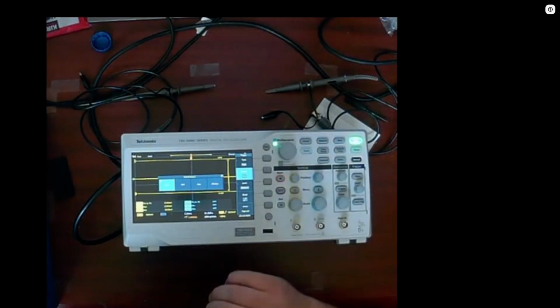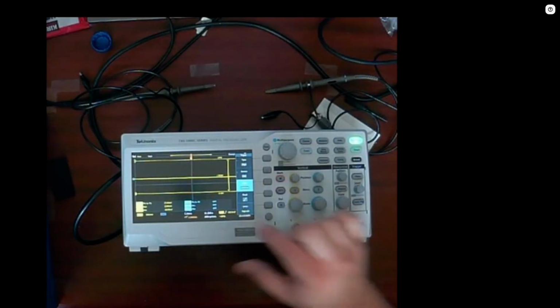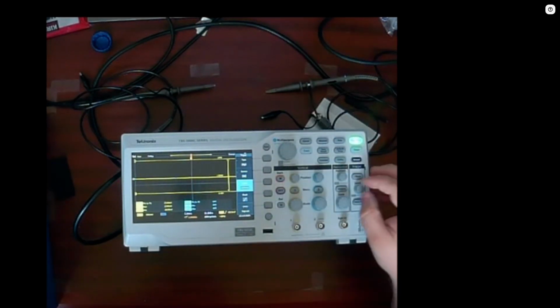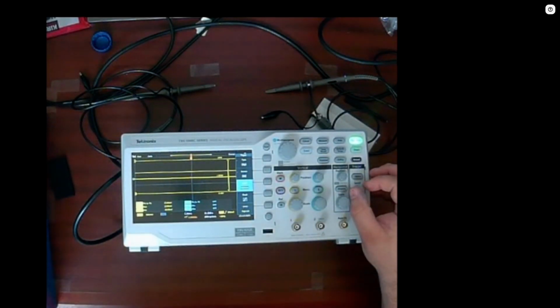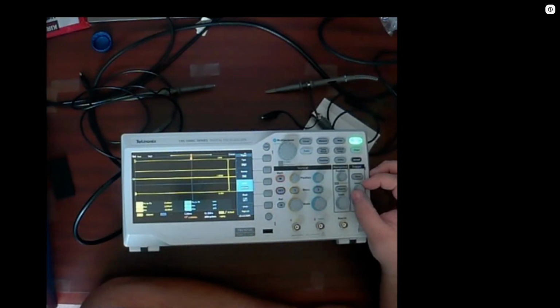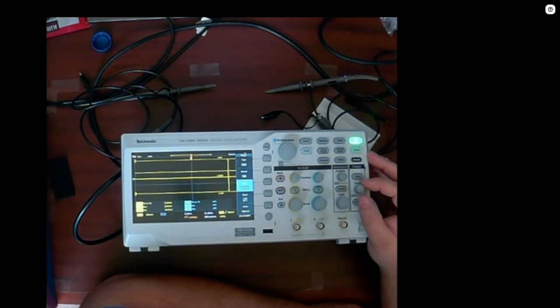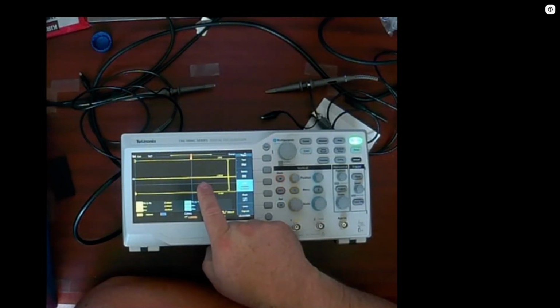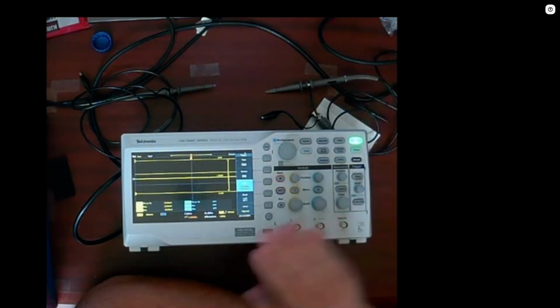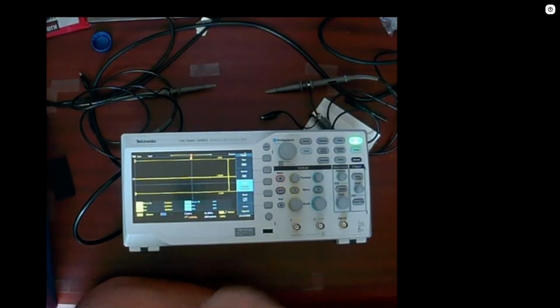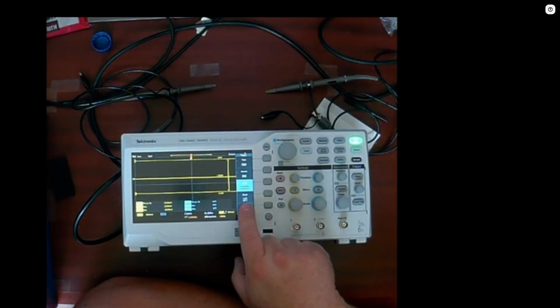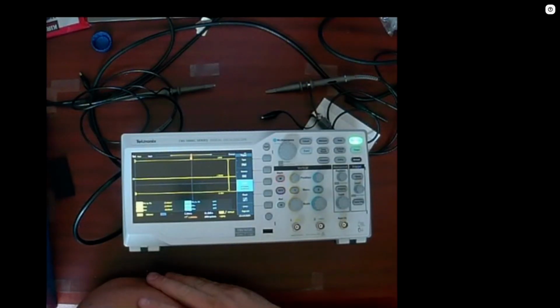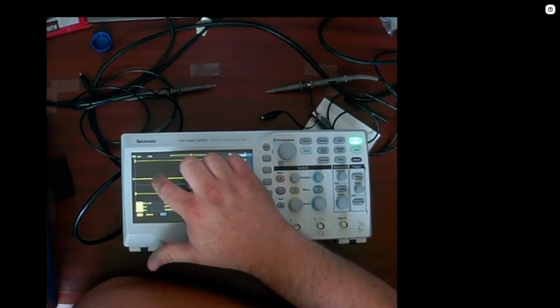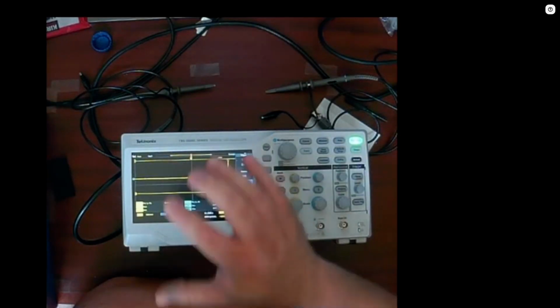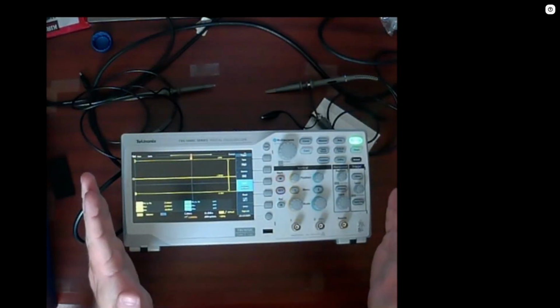Down here is my level. My level is how big of a signal I want it to go to. So if I adjust my trigger, you can see that little line moving up on the scope. That is my level. On here I currently have it set to edge and channel 1. So when channel 1 reaches that line going up or down, depending on how we set it, which is our next option, the slope, either up or down, then the scope is going to say, okay, I have my signal, it's tracing up, it hits that level, now I'm going to lock in, and that's what I'm going to display on the screen.